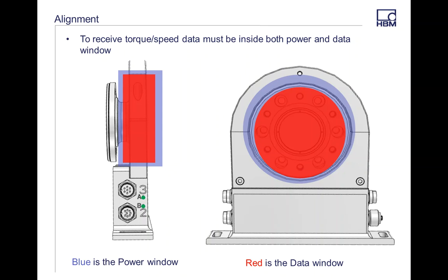Inside of this window is the next little smallest window. That's going to be your data window. Basically, as long as your antenna is in both of these windows, you're going to be getting your data and your power, and all the other information that you're getting from your rotor. For example, like rotor temperature, your speed, and things like that.